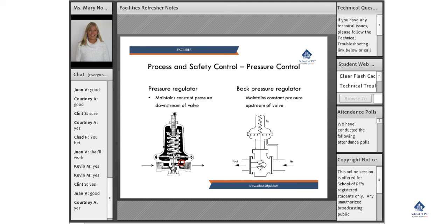The gas can flow through that little opening and put pressure on this diaphragm right across here, which pushes on the spring, and the spring's set to a certain amount of force. If you want to maintain 120 psi downstream, and let's say we don't have enough pressure, it's going to allow that spring to push down and open this seat more.